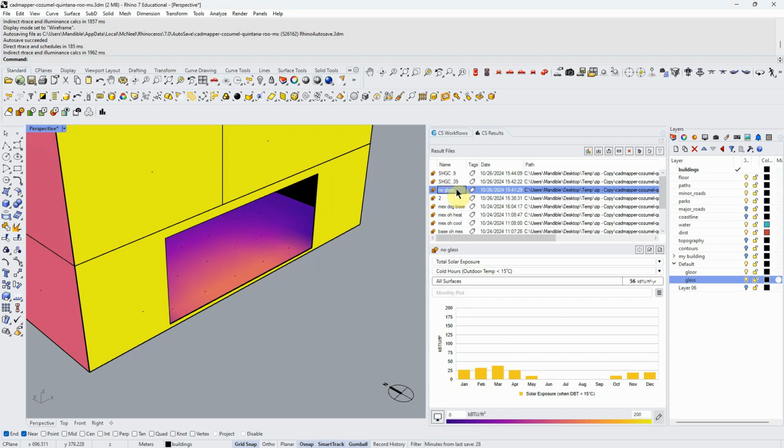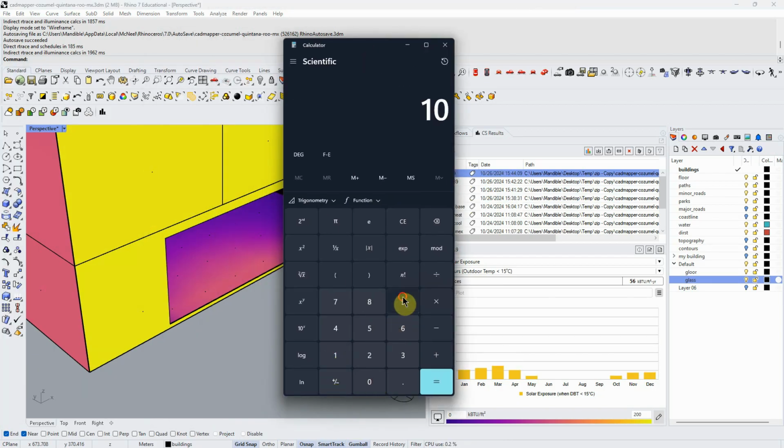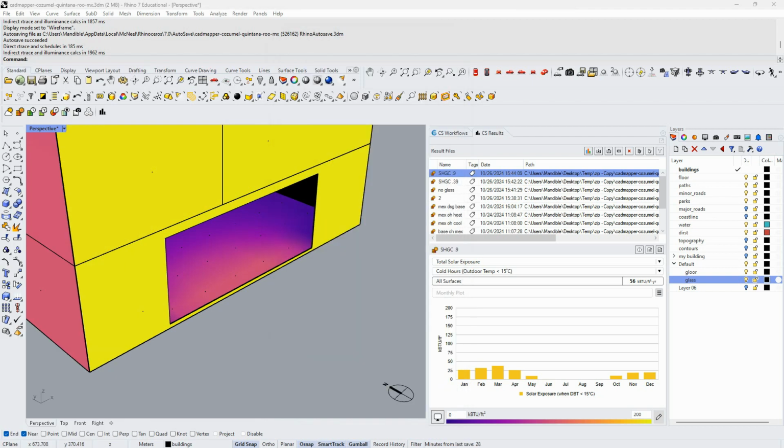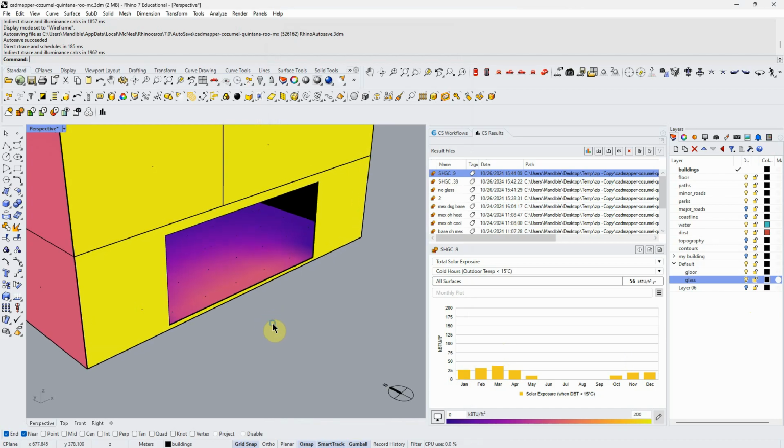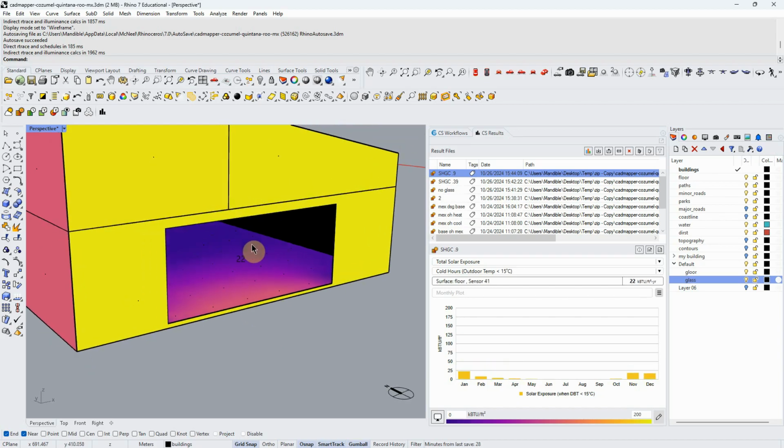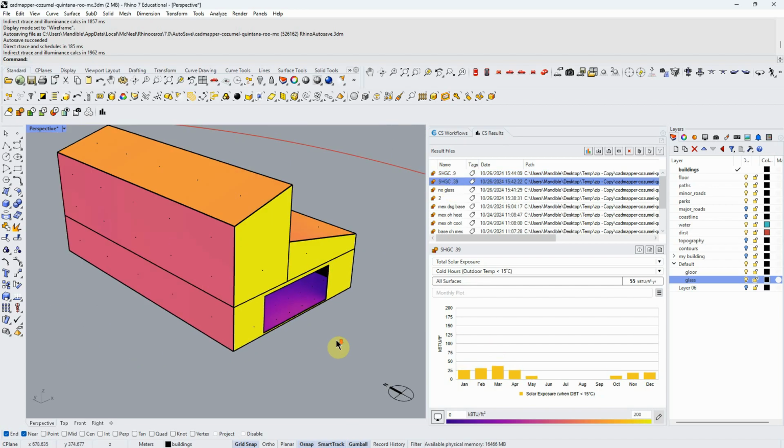And even if we're comparing the 121, I'm just talking about right here at the front, 109 divided by 121, it's about 0.9, so 90%. And we were saying this is a 90% solar heat gain coefficient glass. The other had no glass, so it should be 100%. So that totally makes sense, right? And then you can move from there and see what else you want to do. If you want to make this bigger, or if you want to think about whether it's the same if you go back further in, how it changes. All right, I hope that helps. If not, let's keep going. Just ask me more questions.